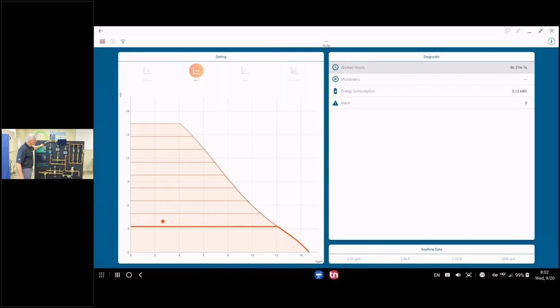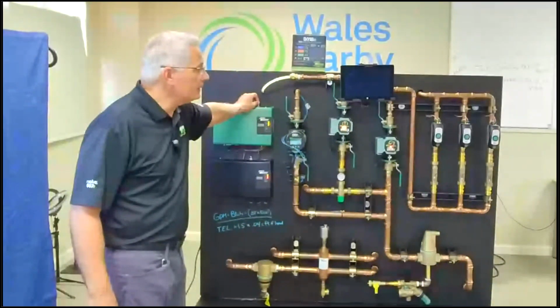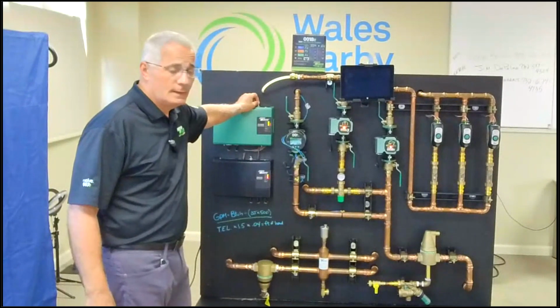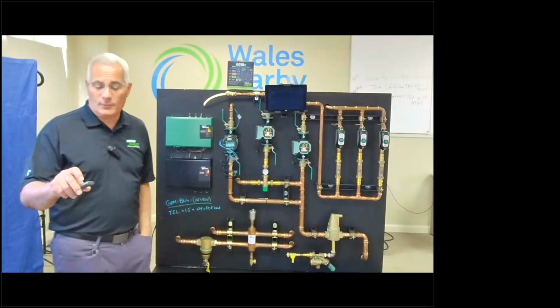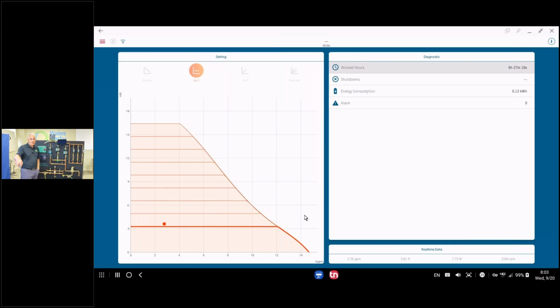So I'm going to turn off the zone. Just give us a second here. That zone valve is going to close. So Chris, if we can go back to the other screen. So it closed. So now my GPM changed to 2.29. Now it's registered 2.29 GPM. Still overcoming just under 4 feet of head, but my watts changed to 7.96. All right, so the wattage went down.